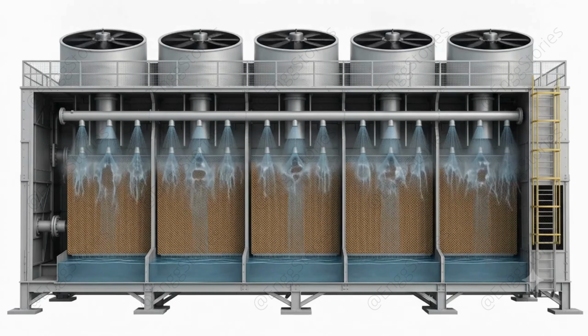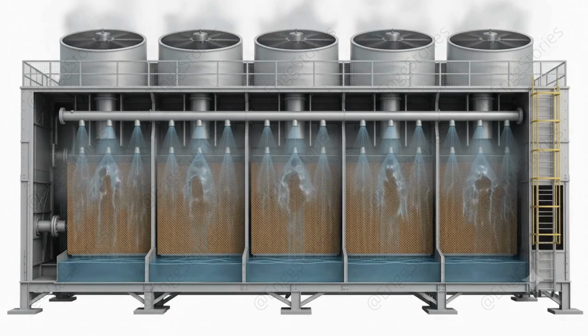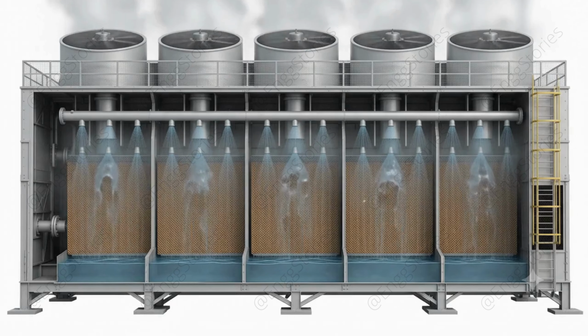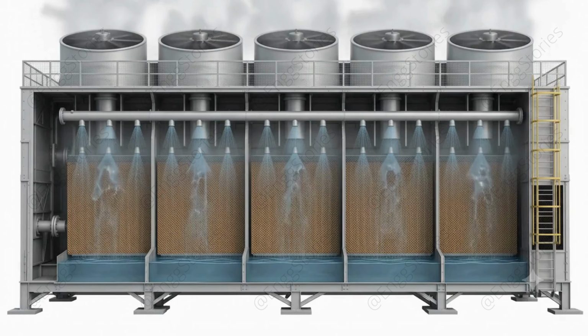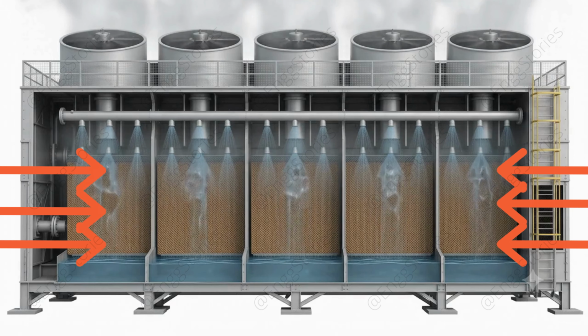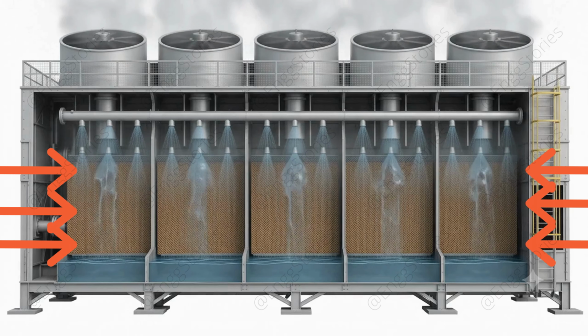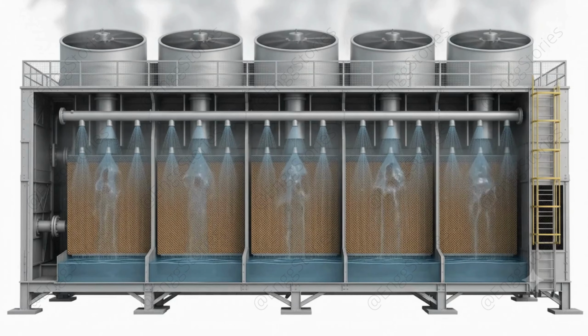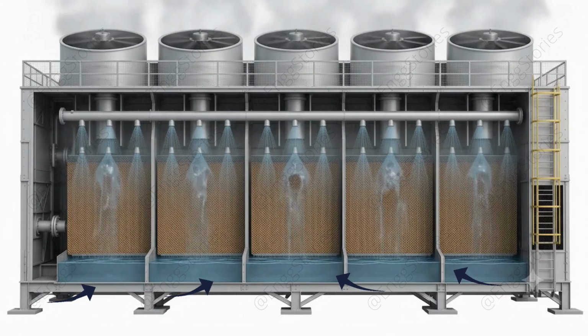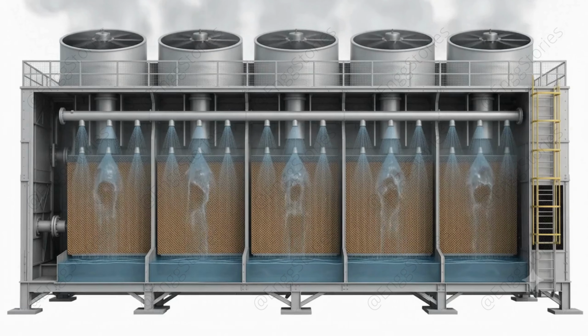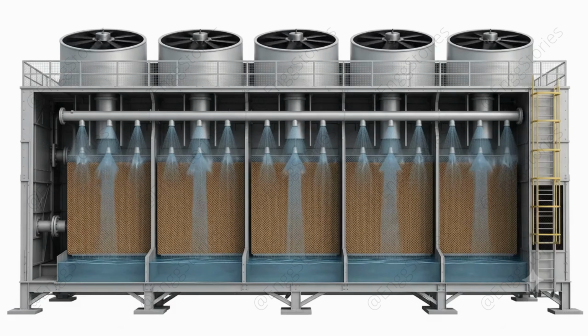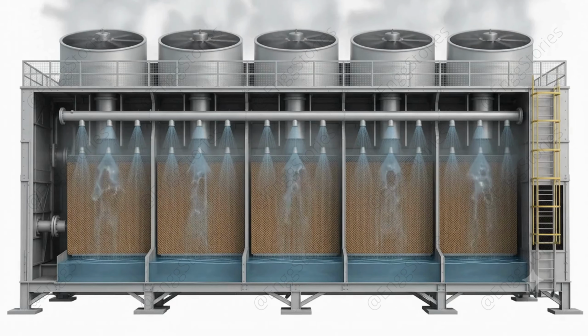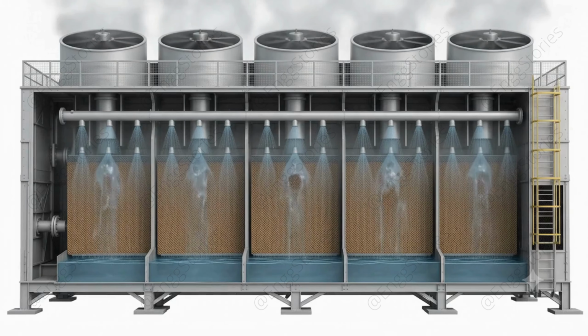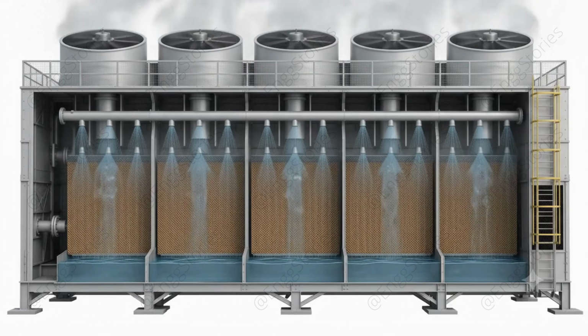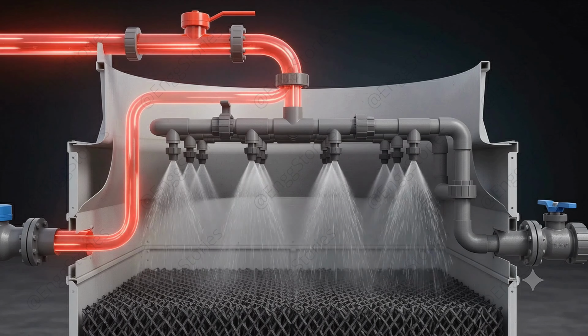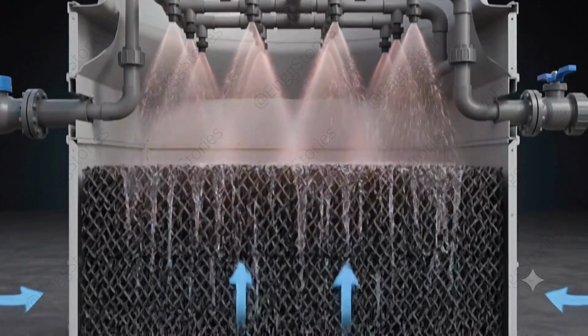There are two main types of induced draft cooling towers: cross-flow cooling towers and counterflow cooling towers. In a cross-flow cooling tower, the air moves horizontally across the falling water. In a counterflow cooling tower, the air moves upward while the water falls downward, so the air and water flow in opposite directions. A cooling tower continuously loses a small amount of water during operation. There are three main types of cooling tower water losses: evaporation loss, drift loss, and blowdown loss.